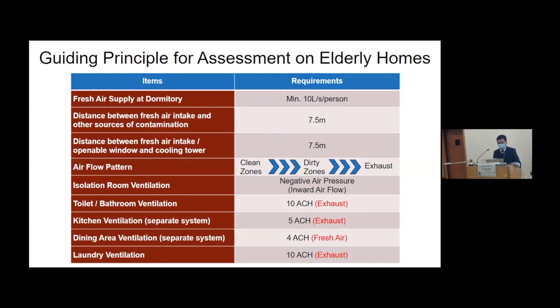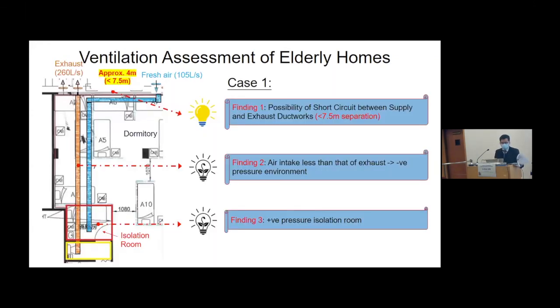It includes the fresh air supply rate at a minimum of 10 liters per second per person, distancing requirements between fresh air intake and sources of contamination, the airflow pattern from clean to dirty, and the minimum ACH for various different areas in the elderly home. And I'm going to share with you some observations in two different cases.